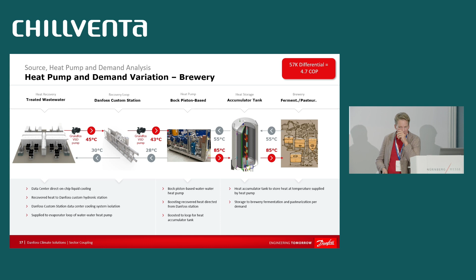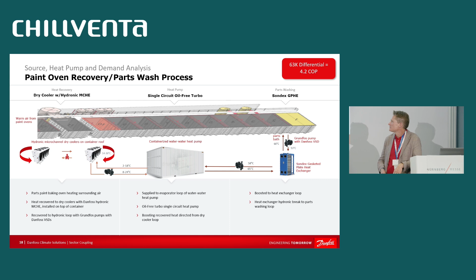This is an example of that. If you recover heat to electrify a brewery's heating system based on heat recovery from a data center, it's about 3 times the efficiency compared to that same brewery using an air-to-water heat pump as an alternative. That's a significant enough opportunity that breweries will pay data centers to co-locate on their site. That's the future sector coupling business model we see forming.